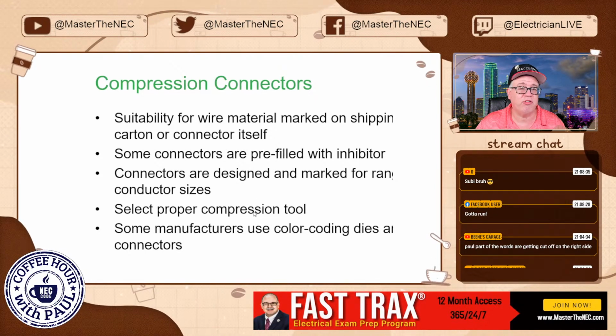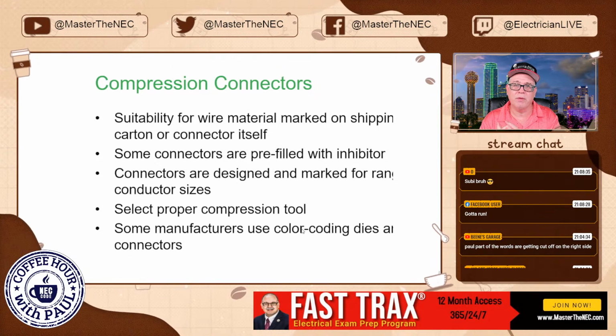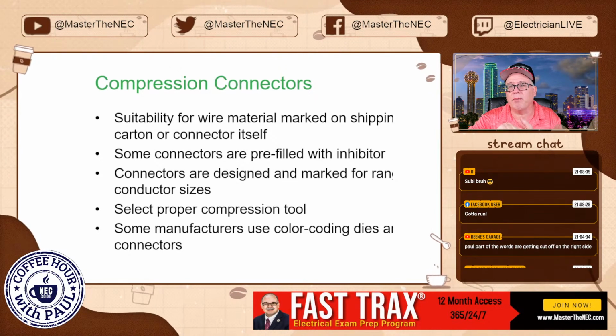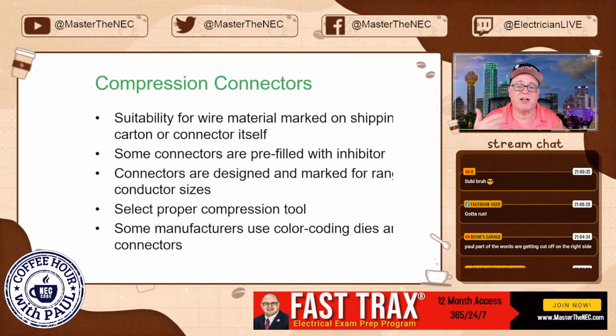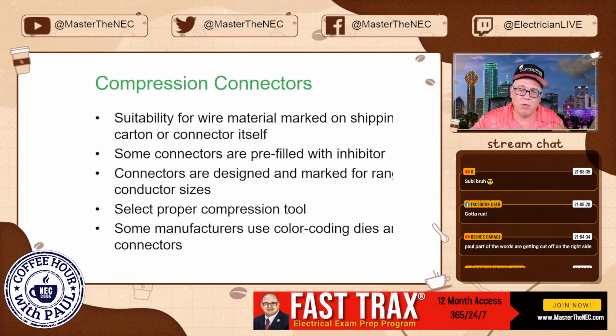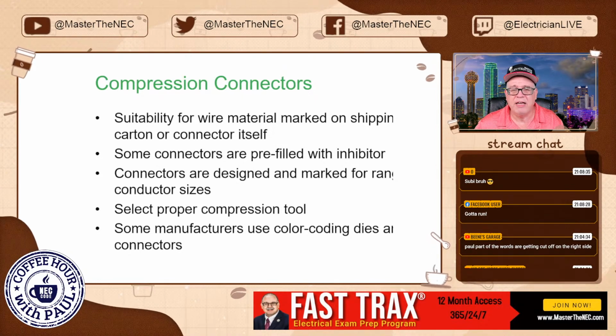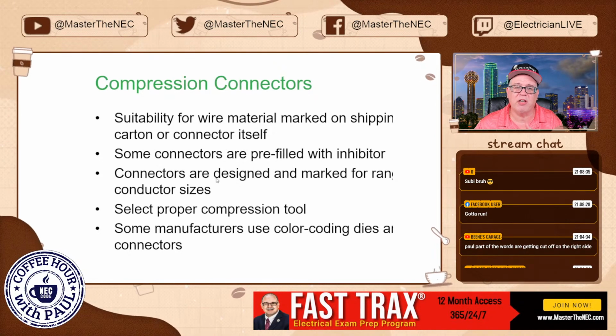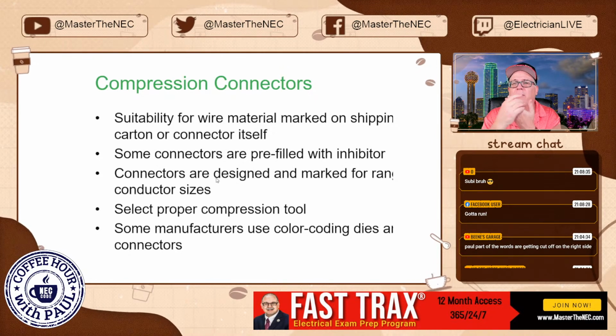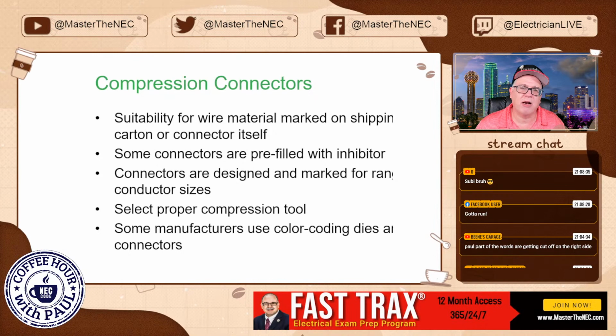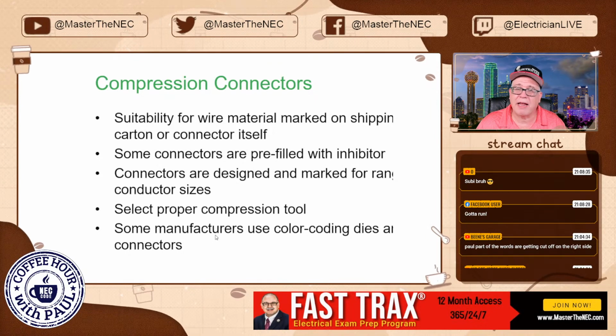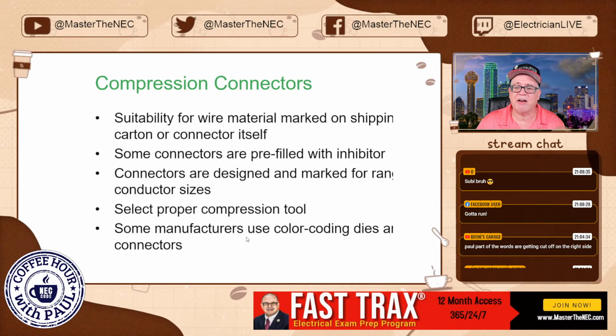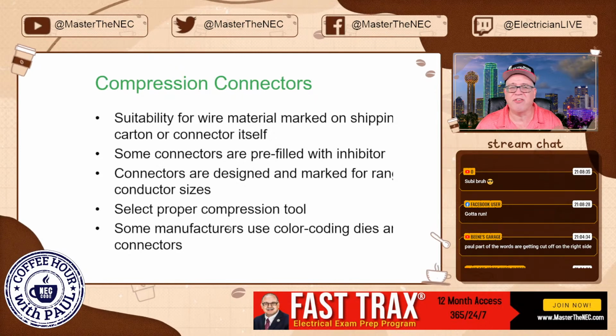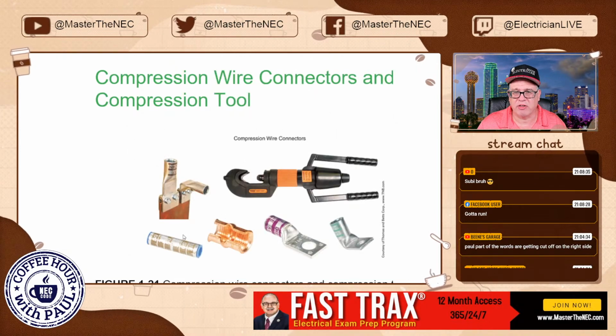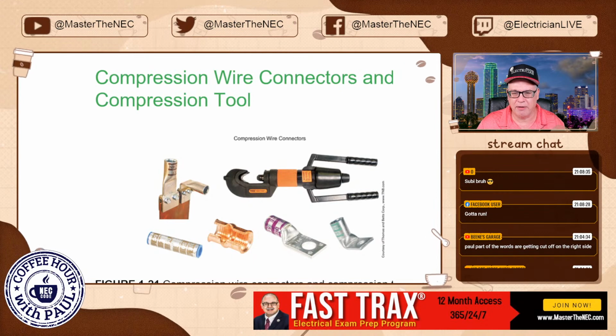Use proper compression tool if you're doing a compression style, okay? Make sure you're using a proper tool. Usually the dies that come with these compressions will tell you the same what you can have, and it's the same way for the connector with compression. It'll tell you how many can go in there per compression. Just make sure you follow the rules. And then a lot of manufacturers like Burndy will actually give you color-coded dies that match their connectors for those connections, right? And here's a good example right here.